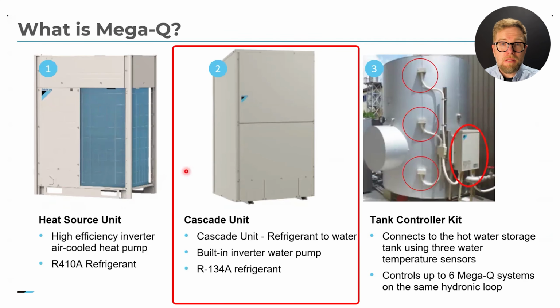Next, there's the built-in inverter-driven water pump in the Cascade unit. Typically, you'd have to spec out a separate circulation pump and do a bunch of guesswork to size it properly. With the MegaQ, the pump is already integrated and it automatically adjusts flow rates. That means fewer external components to install, faster commissioning, and hopefully smoother, more reliable operation over the life of the system.